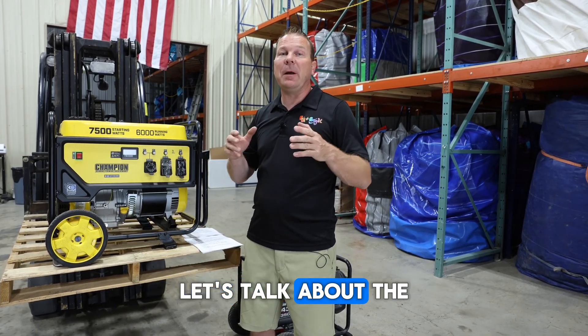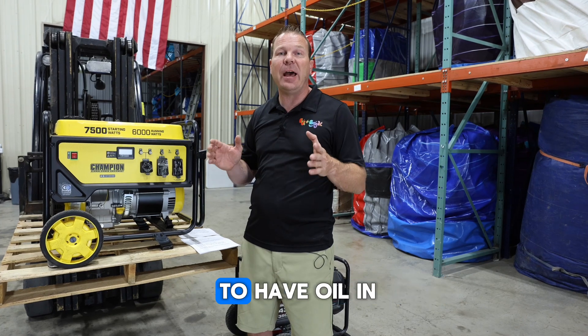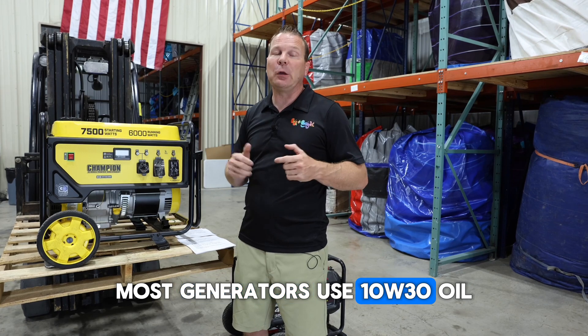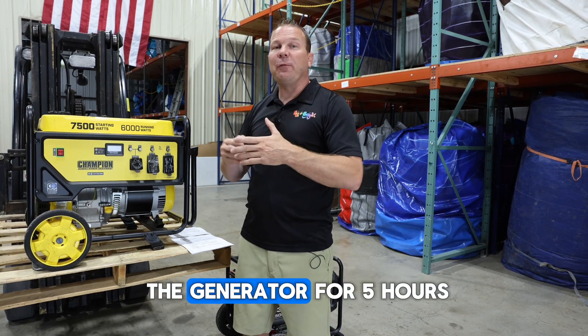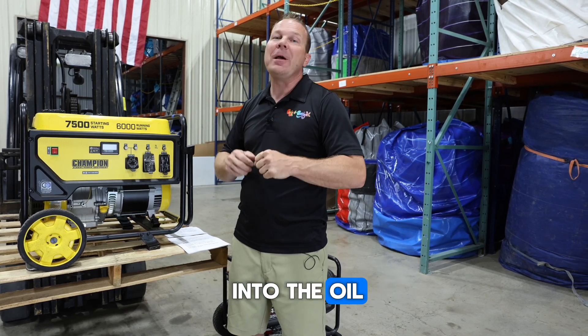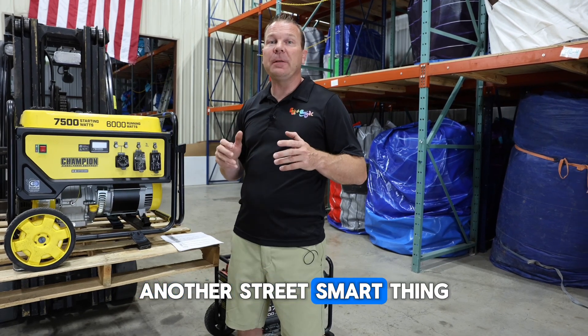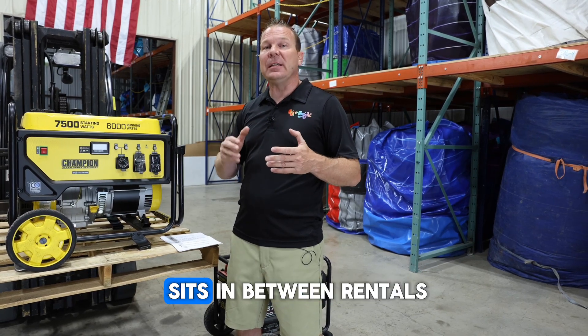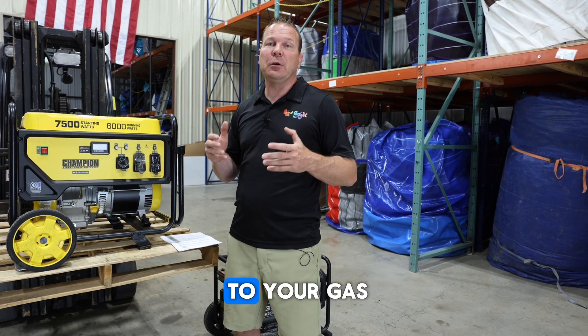Now you've bought your generator — let's talk about the things you need to know. Most generators ship without any oil in them, and it is absolutely necessary to have oil in this machine. The first thing you need to do is fill the oil to the top; most generators use 10W-30 oil. The second thing — and most people don't do this — is you need to break your generator in. Run the generator for five hours on a very light load to get the motor going and let all the metal shavings work their way out into the oil. Then drain the oil, put new oil in, and your generator will be properly broken in. Also use fresh gasoline; gas can start to go bad even after 30 days. If this generator sits between rentals and the gas starts to go bad, you can have issues. It's always good to add a fuel stabilizer to your gas to help prevent that.